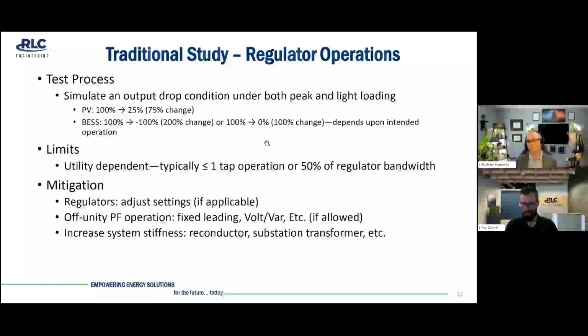Regulator operations, this is another output drop condition that we're looking at. We're typically looking for tap operations to be less than or equal to 1 tap for a given transition, or the other common utility practice we'll see is 50% of the regulator bandwidth. Now, it's important to consider here that if you're looking at 50% of the regulator bandwidth, you're usually looking at the terminal voltage of that regulator. And if it is operating within a line drop compensation scheme, the terminal voltage of that regulator is not representative of the number of taps that it may see.